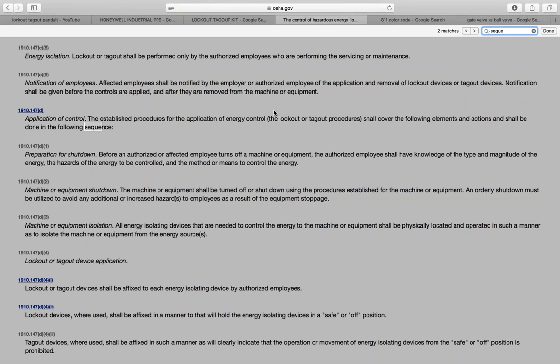We're going to replace and reactivate all the safety controls, put everything, all the guards, devices back in place. We're going to remove the locks and the tags and isolation switches, and each employee is going to either remove their own or log in. We're going to log each employee knowing that they're no longer in an area where they may be harmed when we re-energize. And we're going to notify all affected personnel that the lockout tagout's ended, and then we're going back up live. And then we're going to operate or close the isolation switches, and restore the energy.